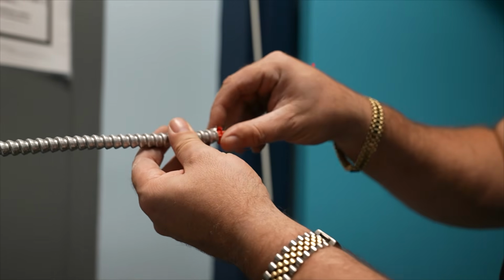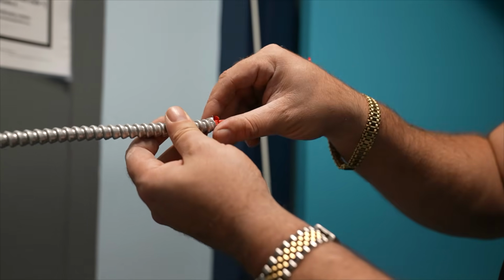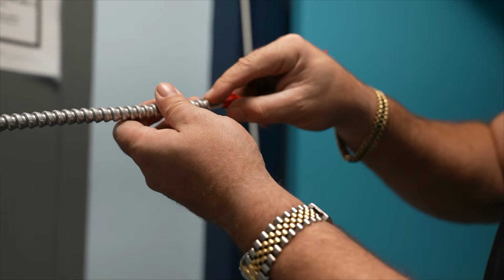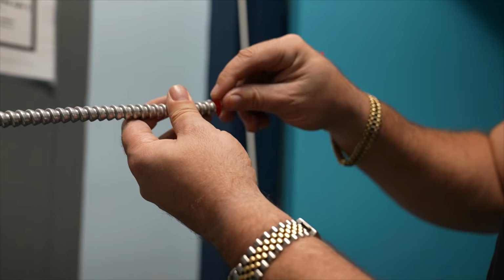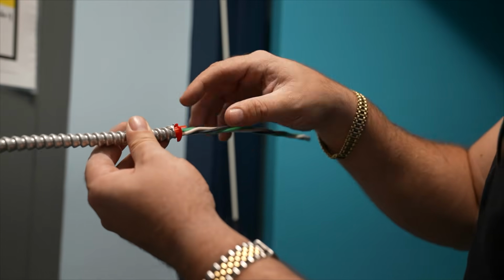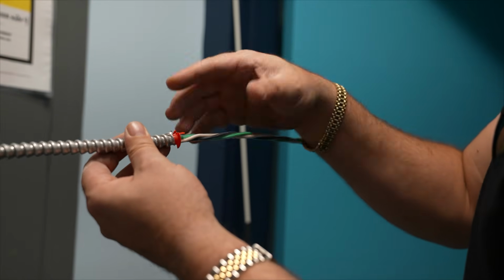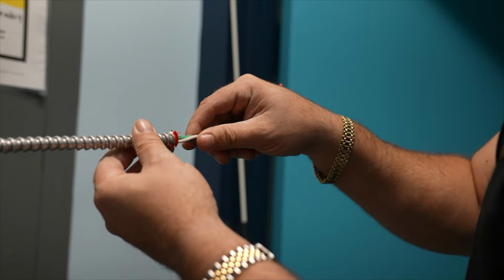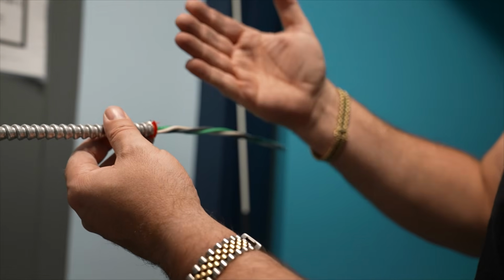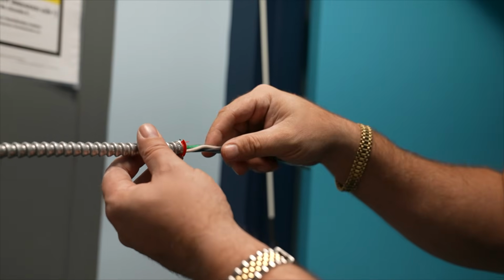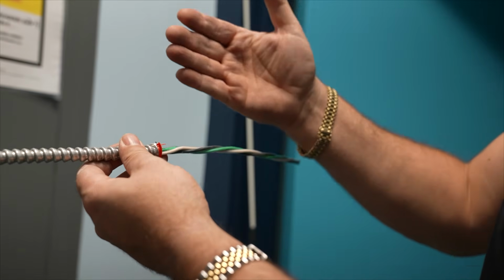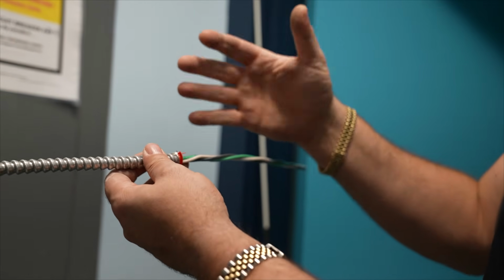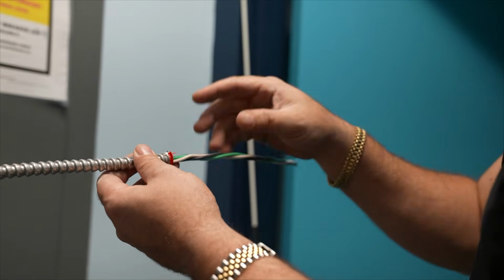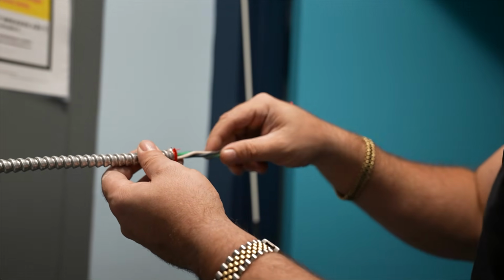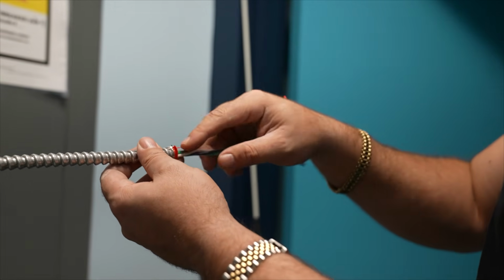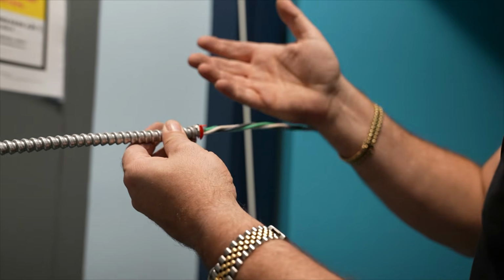But even still with the anti-short there, if it ever were to come out, there's a danger that sharp edge could potentially abrade the wire, cut it, or wear it, because wires do vibrate at a very high frequency - 60 hertz in America. You wouldn't be able to see it, but it vibrates. So over time, it could potentially wear and short in that spot. That's why these are called anti-shorts.